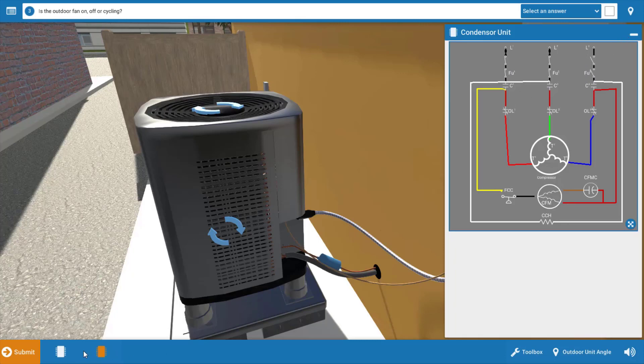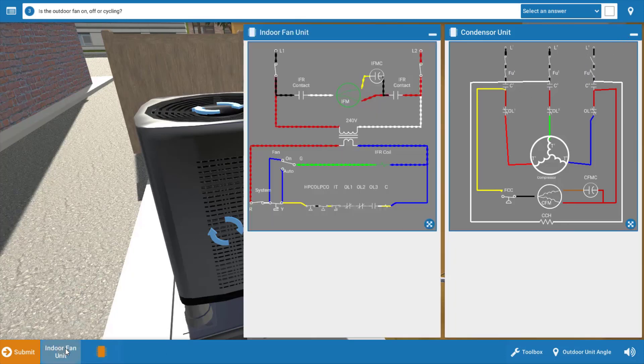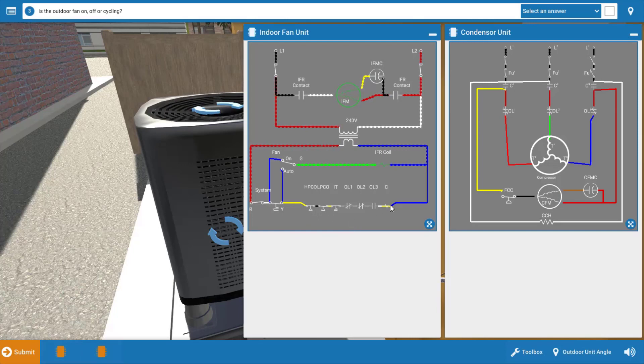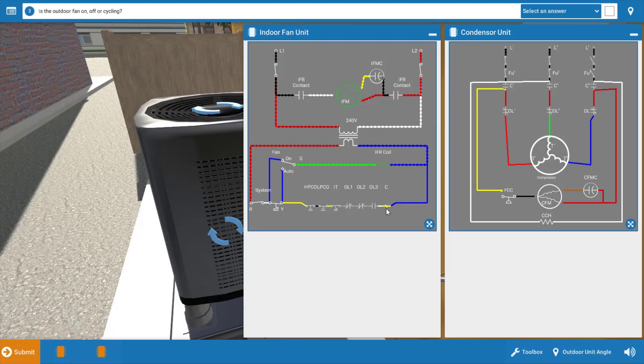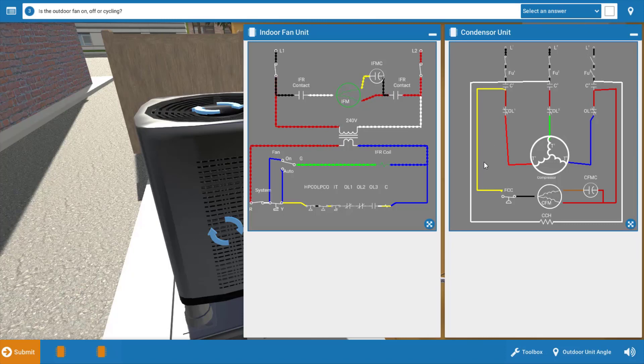But if we go to the indoor unit wiring diagram, we can see that the contactor coil right here at the bottom right, when energized, will close these contacts up top here, the three sets of contacts. Again, this is a three-phase compressor motor, and it's going to require a three-pole contactor.